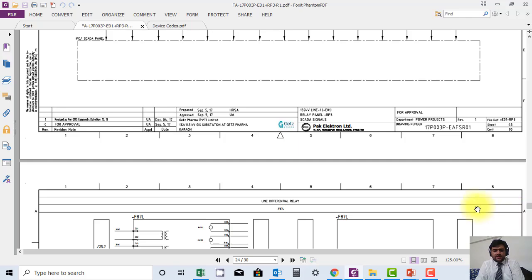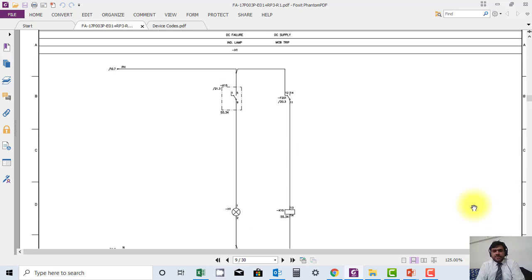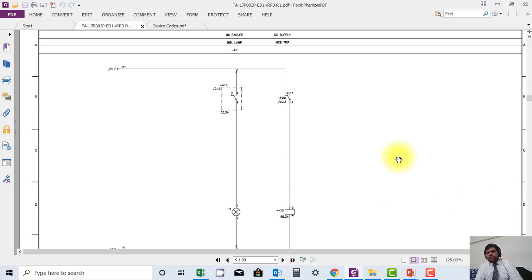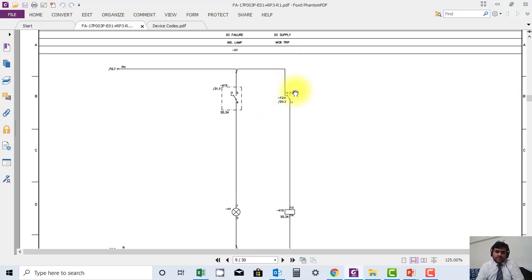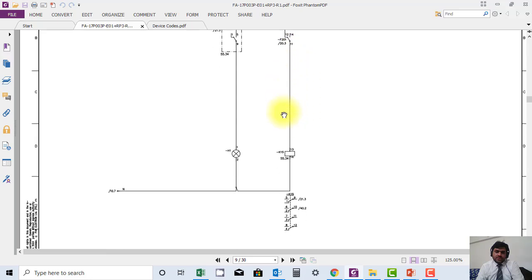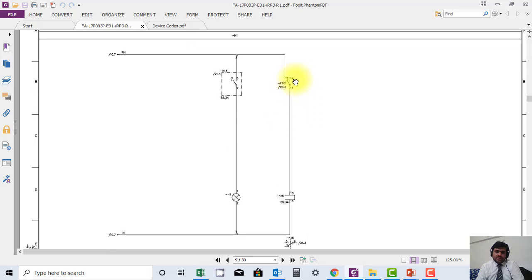In this drawing specifically, they have not used DC supply end-of-loop supervision, but they have used basically an MCB. If the MCB trips because of any fault, then this contactor contact will operate and the contact will pick up.